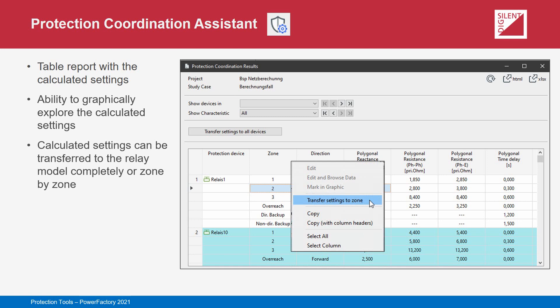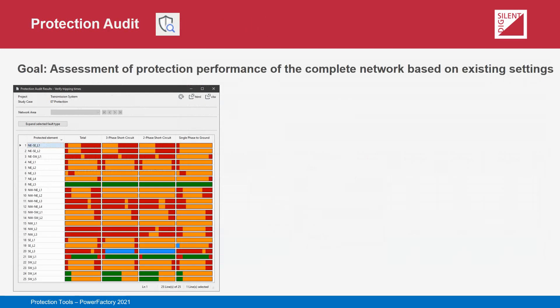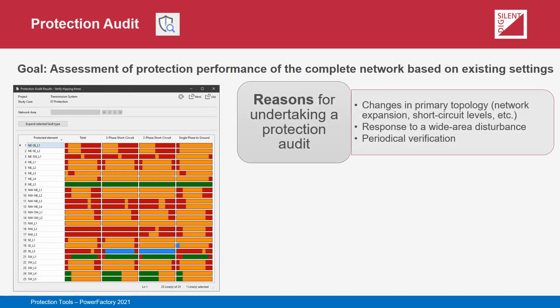With the settings transferred to the relays, calculations and simulations can then be performed on the network model and the performance of the new settings can be analyzed in detail. The Protection Audit tool is used to evaluate the performance of an existing protection scheme where the settings of the relays are already known. The tool will identify weaknesses in the scheme and classify the issues in a concise colour-coordinated report according to severity. Possible reasons for undertaking a protection audit include capturing the impact of changes to the primary topology of the network caused by its evolution over time, and seeing the response of the protection scheme to wide area disturbances.